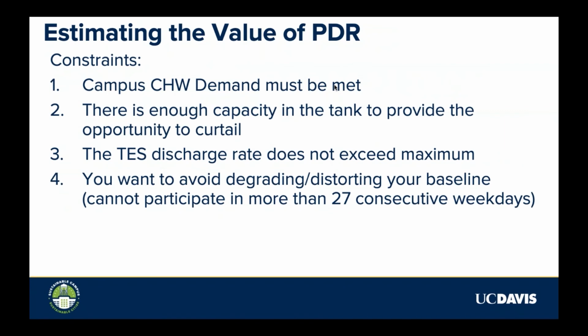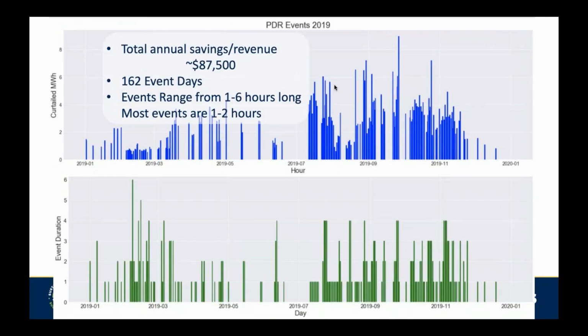The constraints are that the campus chilled water demand must be met, that there's enough capacity in the tank to provide the opportunity to curtail, and that the TES discharge rate doesn't exceed maximum. You also want to avoid degrading or distorting your baseline, so don't participate more than the number of days you have to add to your basis for your baseline calculation.